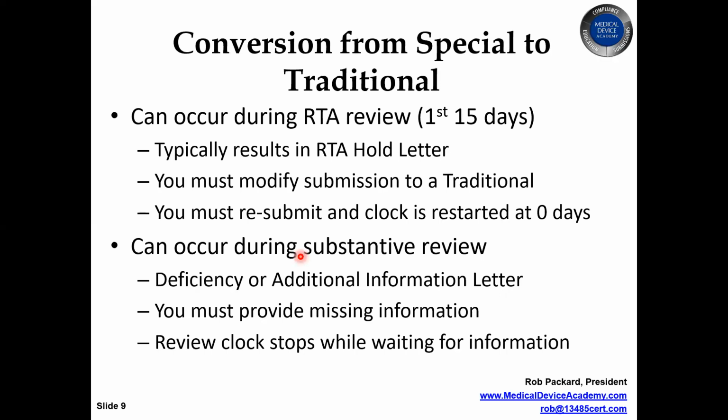This will be a traditional 510K. And when that happens, they switch checklists. They go over to the longer form for a traditional 510K, and they start answering the questions. And because you've designed your submission for a special 510K, you don't meet the requirements of a traditional 510K, and you get an RTA hold letter.